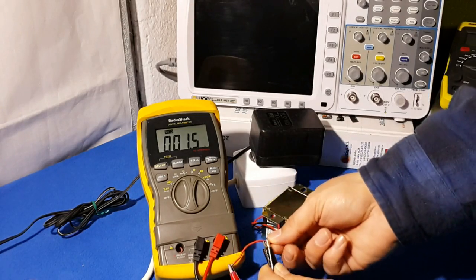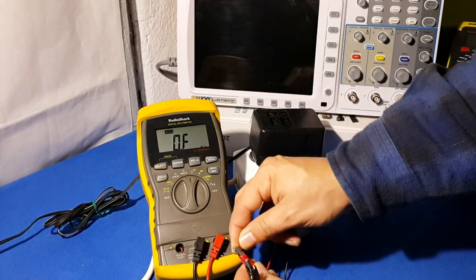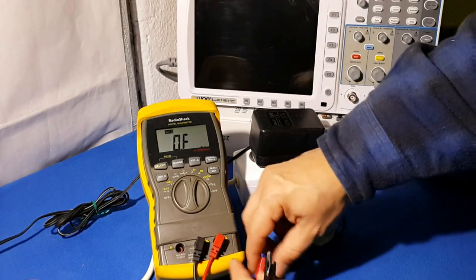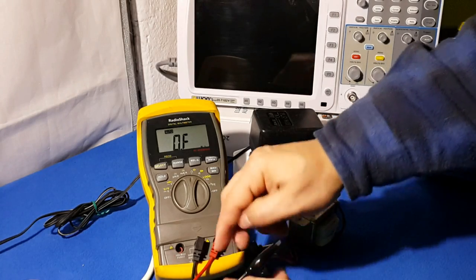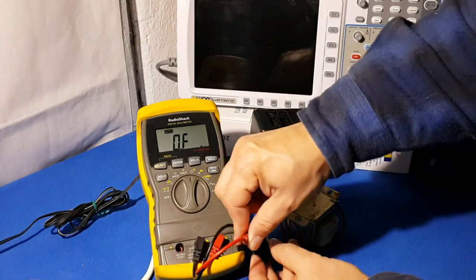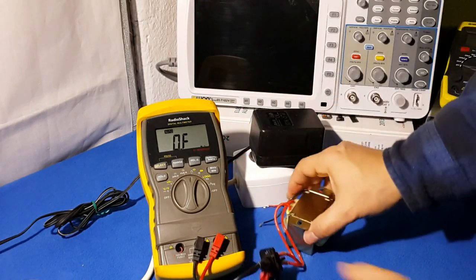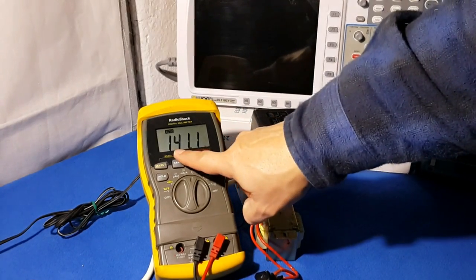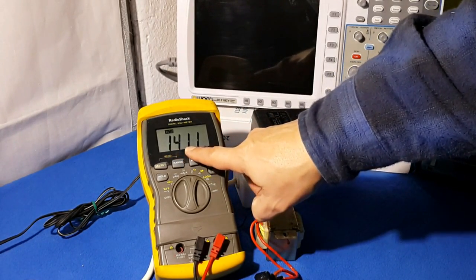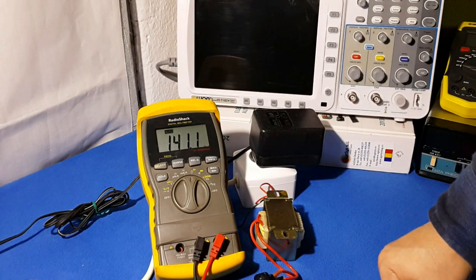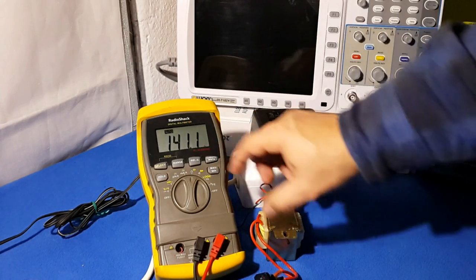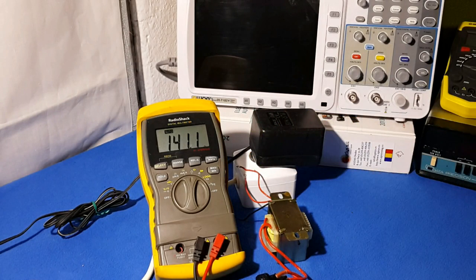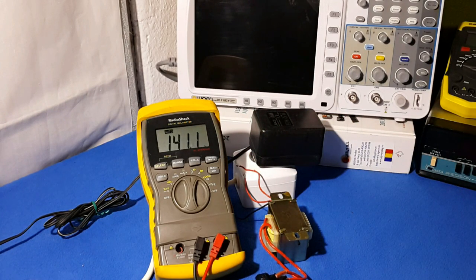In the primary, we're expecting to get higher resistance than the secondary. 141 ohms, and the other was close to zero in the secondary. This one, the higher one, is the primary. So now we know how to test them. Thanks for watching.